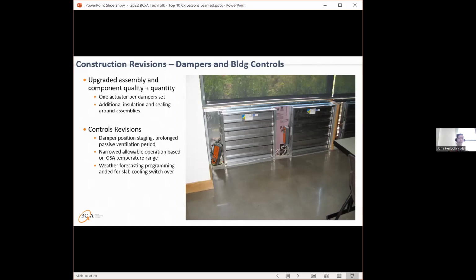And then we also did a lot of controls revisions on this project. Damper position staging, and a prolonged passive ventilation period, so that you would use natural convection. That was both an energy thing and trying to prevent large drafts into the building. And then we narrowed the operational range of when these dampers can operate based on outside air temperature, so that we didn't have 55-degree air coming across people's legs, even if they needed the cooling. And then we functionally tested the slab, vetted the slab out for slab cooling.